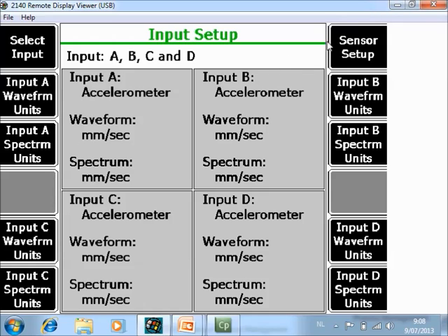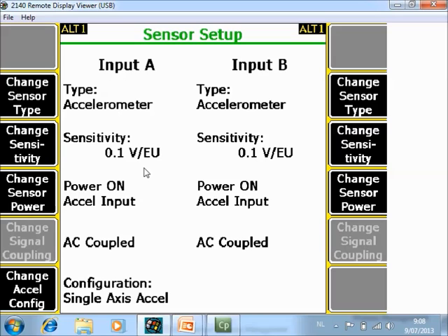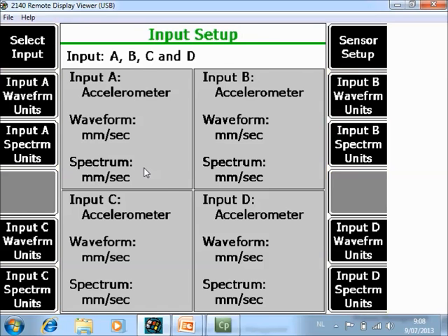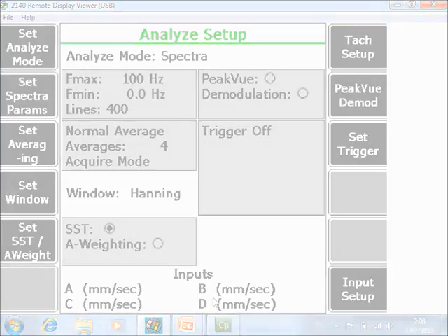If that is not correct you can change it by sensor setup F7. I have accelerometers with 0.1 volt per engineering units and power is on. If you are using different sensors you can specify it here. Now you are ready to collect data with the SST technology on 4 channels simultaneously.